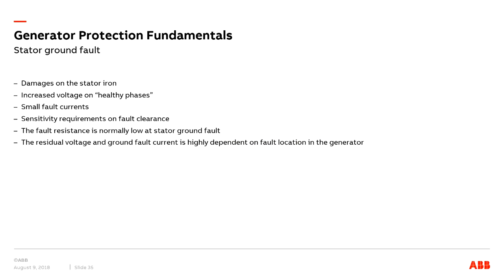Now we move on to the stator ground fault protection. The stator ground fault will result in current flow into the stator core, and as the stator's main core is laminated with insulation between the layers, the ground fault current will influence the insulation between the layers and enable induced additional current flow in the stator. The consequence will be that the stator iron core will be destroyed and needs to be replaced.